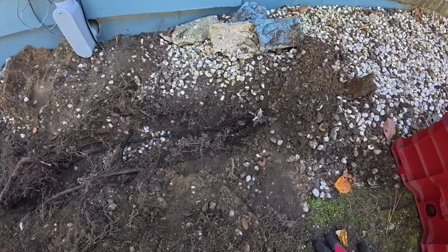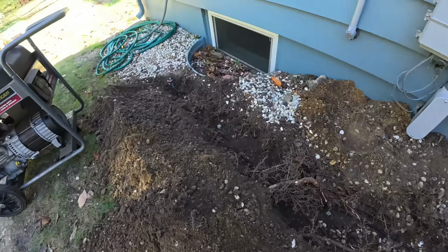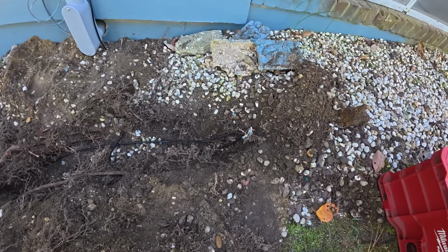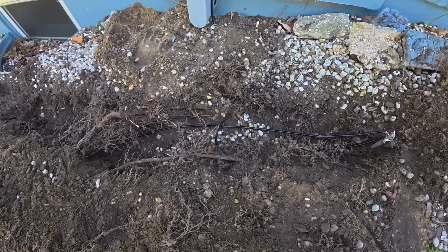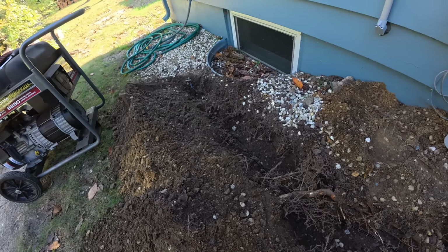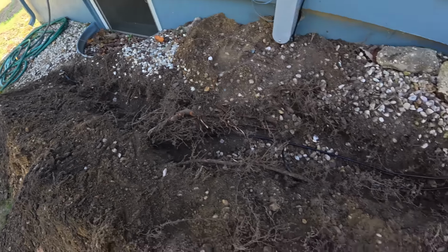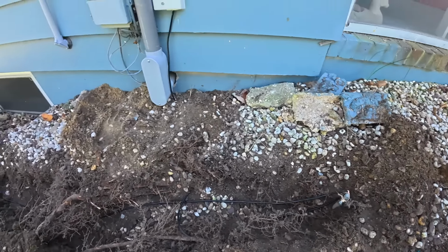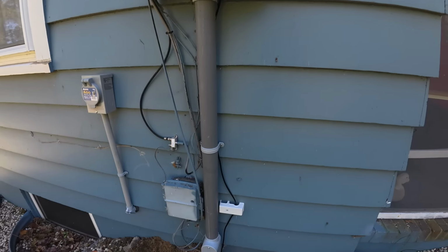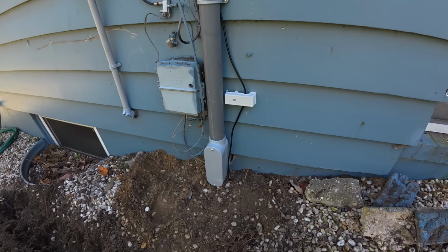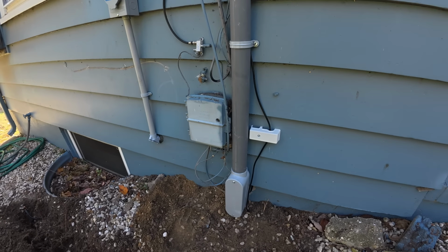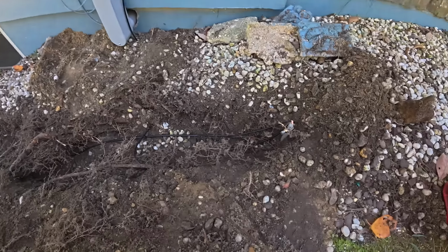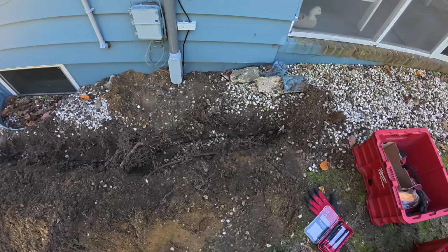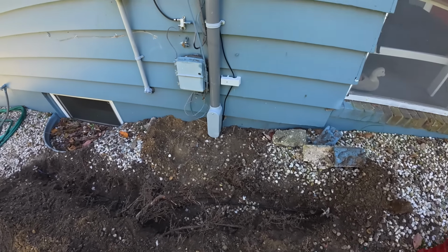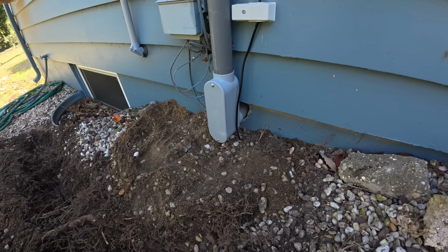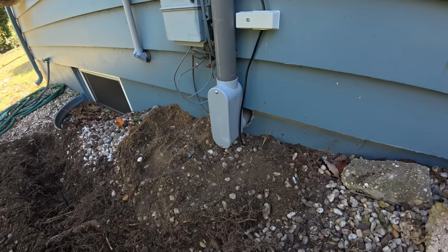So okay, we got our ground rods properly spaced 6 feet apart from each other, because these supplement the copper water pipe grounding electrode, I should say. Code is kind of quiet on how deep we need to make this trench, but we do need to make it so that it stays buried. So we just go from the main disconnect here down behind that conduit. We hit the bonding bridge terminal there for all our grounding electrodes on the exterior for that ground wire for the telephone service. Then we come from one ground rod to the next ground rod, and now we'll bury it up. Next step is to start concreting the old foundation that I made a little bit bigger, and we'll get that airtight with some hydraulic concrete there.